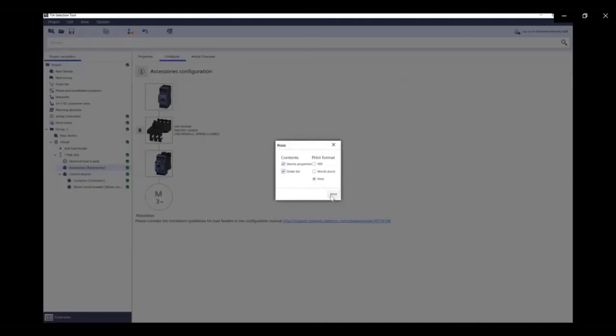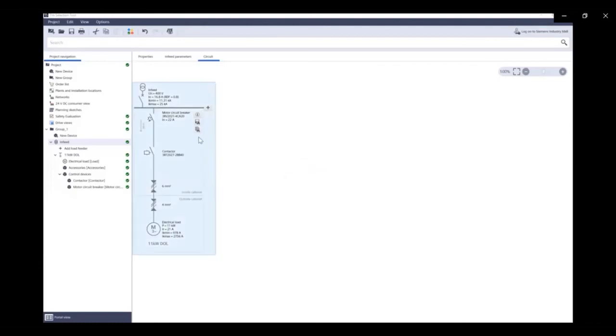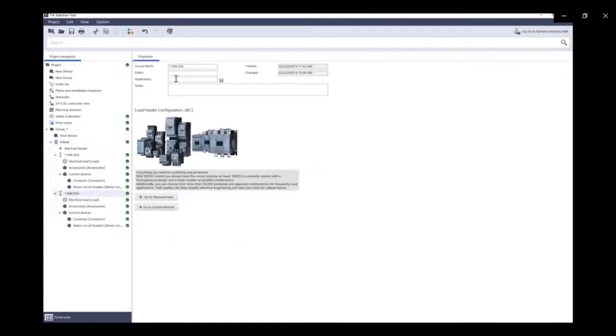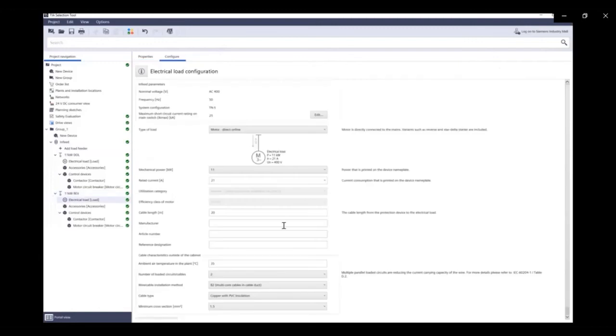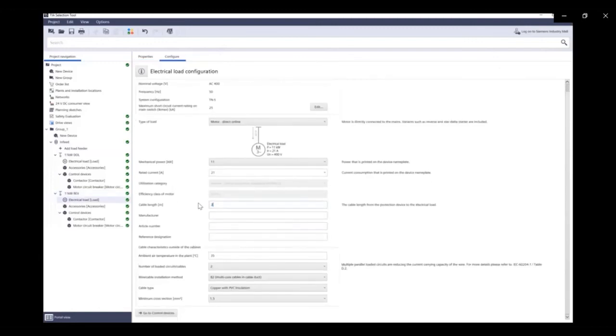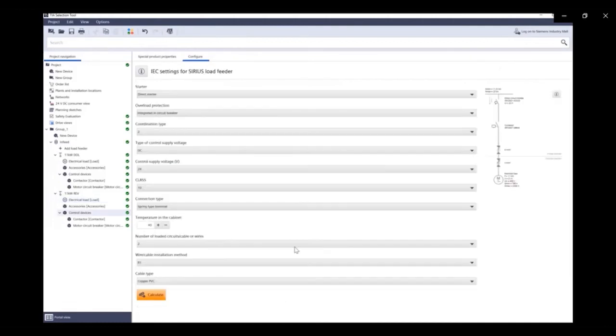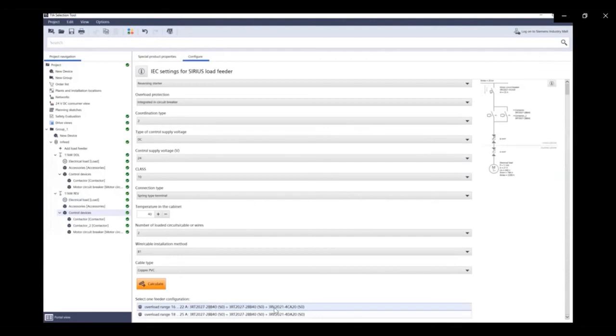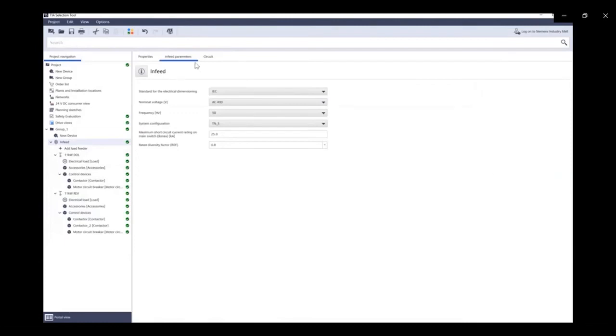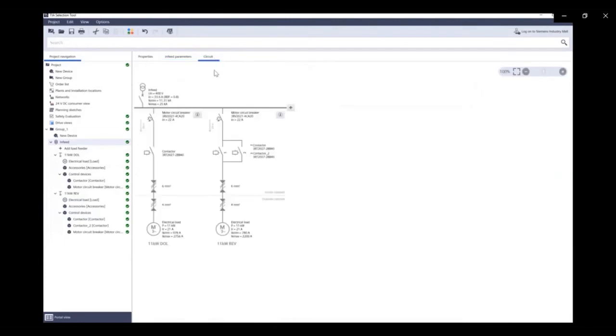So for printing of the documents, I select what I need and start printing of the documents for my technical documentation. Easy copying of the existing circuits and modifying the existing circuits to the application demand is quite easy. That's intelligent software tools provided free of charge by Siemens, shown here for the example with a different load feeder for reverse starter, and with the same procedure calculating the protection and the switching devices, the options being shown here and selected, and automatically calculated the right dimensioning of the conductor material as visible shown over here.